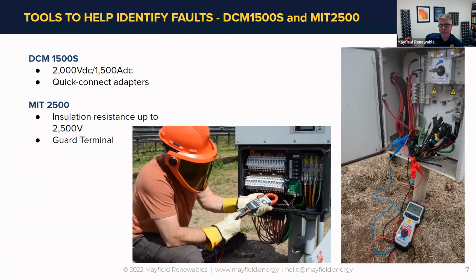There's actually a wet test that they recommend. It's kind of the second level of testing, if a problem is arising and you don't find it with the standard method. Getting the array wet, getting the conductors wet, and doing your testing that way will help exacerbate any potential ground faults and help identify them. If you can isolate strings or different sections of your array it's easier, but on a multi-megawatt ground mount system getting everything wet isn't the easiest thing to do. It's much different in a small commercial or residential application, but that's a way of trying to pull out that intermittent aspect by doing wet tests. Those are in the IEC standard, so I'd recommend taking a look at those tests.